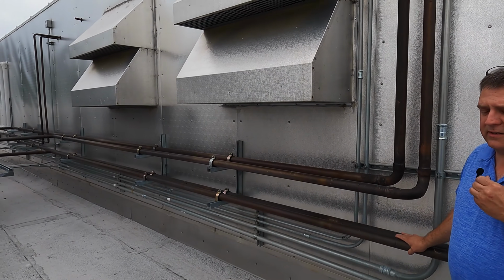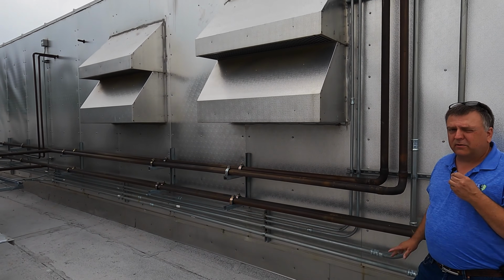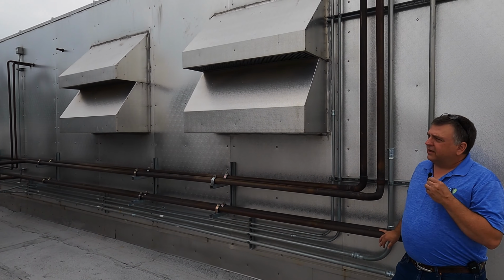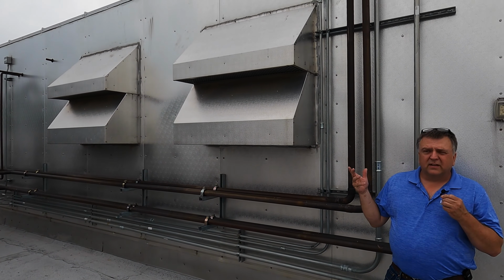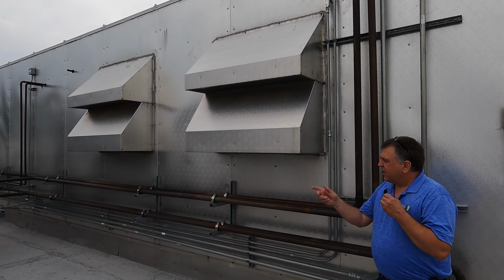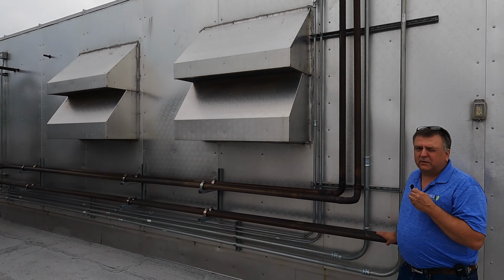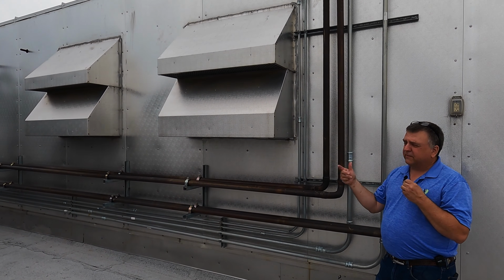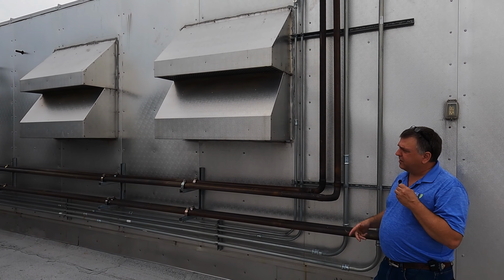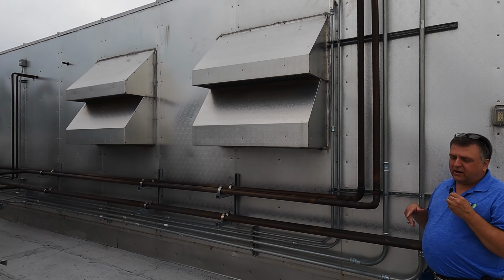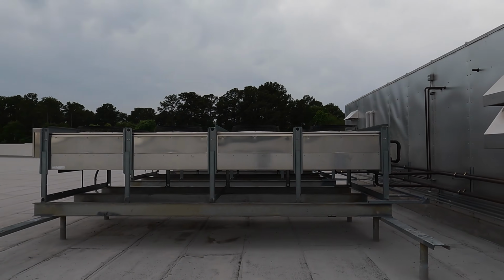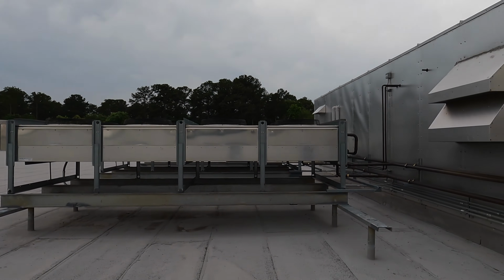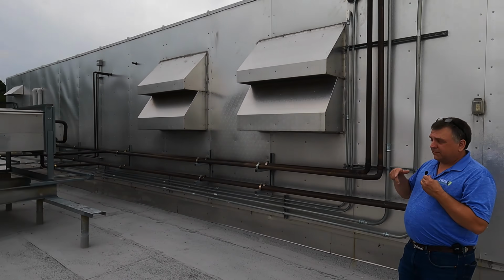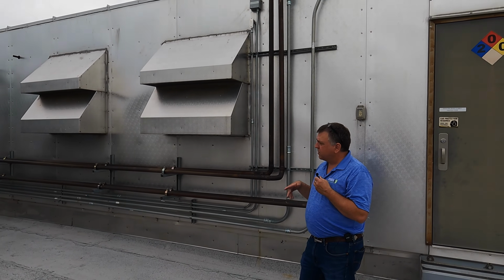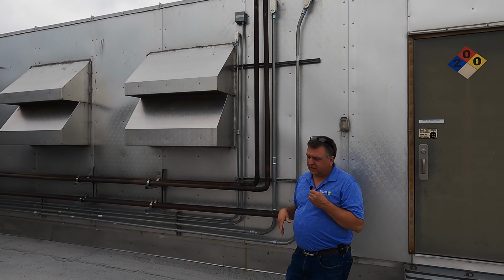Liquid coming out of the condensers is always going to be whatever your ambient condition is. So if I have 67 degree outside temperature, I'm probably going to have 67 degree liquid if I have enough refrigerant in there. If you don't have enough refrigerant in there and you're coming out flashing, all bets are off. And same goes for an outside temperature of 95 degrees. I can only cool the liquid. I've got it changed state, but it's only going to get as cold as its outside condition.